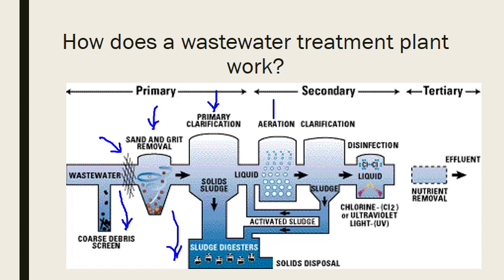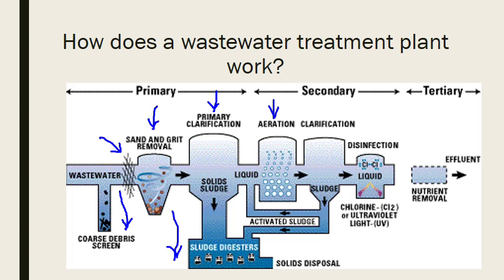When we move into secondary treatment, we are talking about biological and chemical processes. The first step of secondary treatment is the aeration tank, where oxygen is pumped in to allow bacteria to break down oxygen-demanding wastes. That influx of oxygen encourages digestion and allows those component parts to be removed.